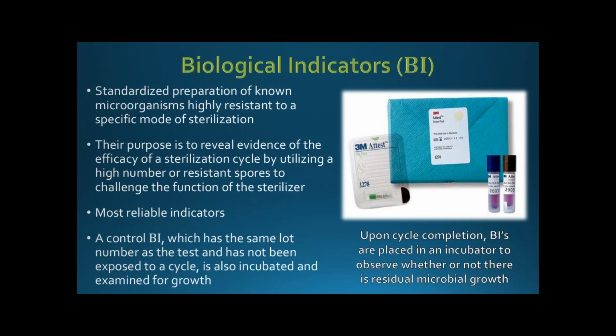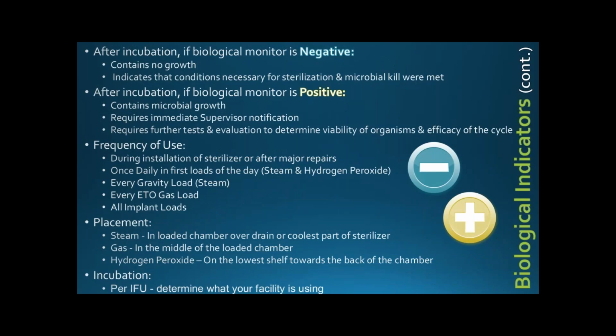So the BI, you always want to have a control with the same lot. So after incubation, there's a lot of different BIs out there right now. Chemical indicator. We have a lot of different biological indicator brands out there. So I know there's a 30-minute BI that's out there. There's a 1-hour BI. There's different types of BIs that are out there.